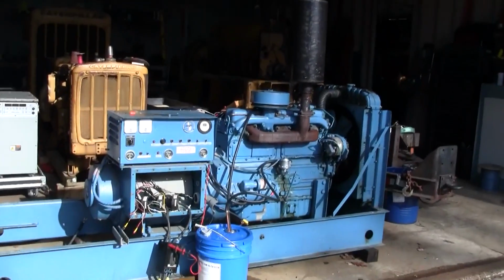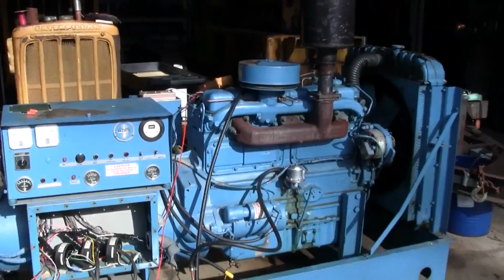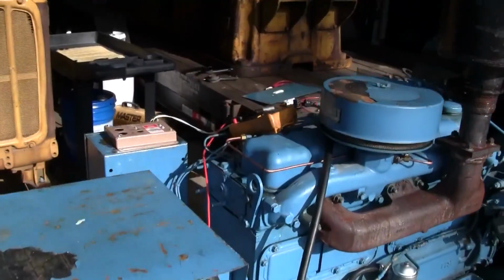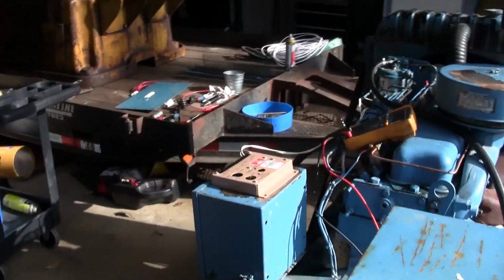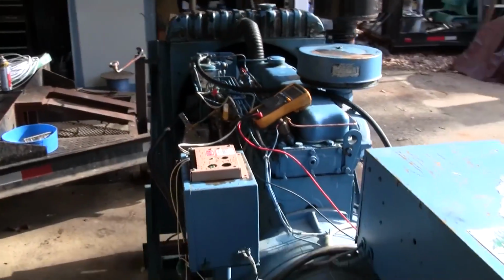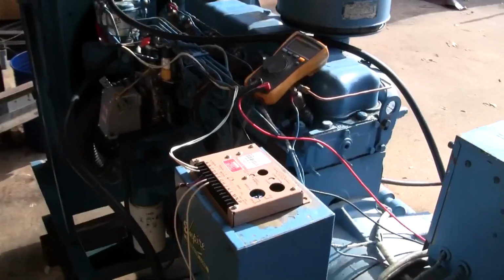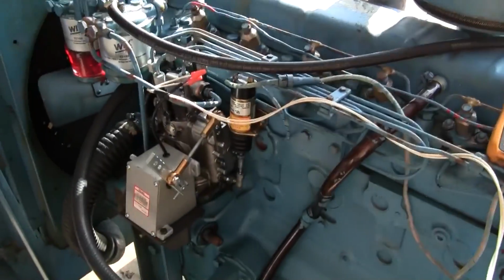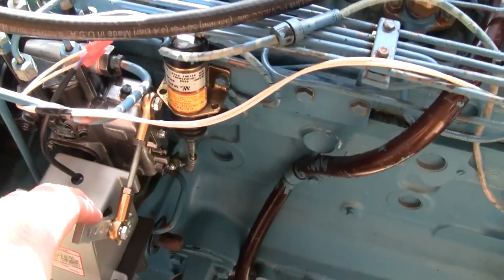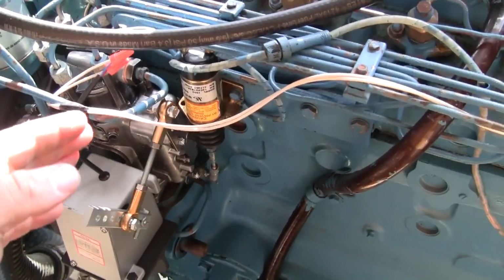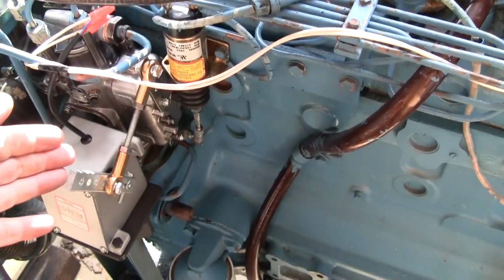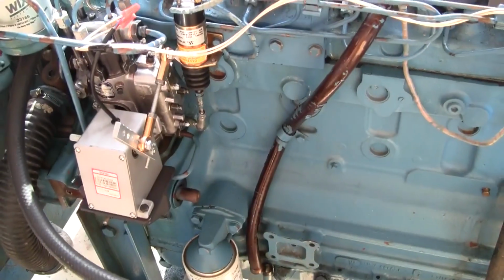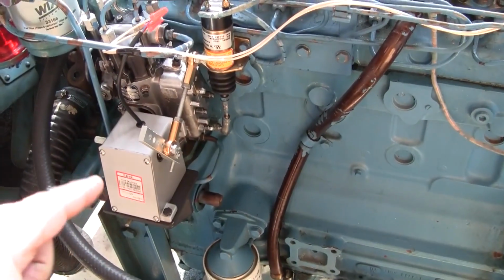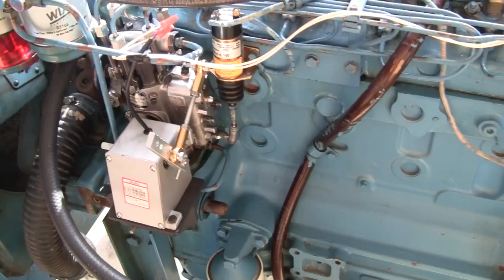Alright, well, I'd consider that successful. I'm quite pleased with the performance of that governor. You know, we were holding 60 to 60.1 hertz between no load and full load. Of course, there's going to be droop. There's going to be a lag. When you dump a heavy load on it, there's going to be half a second or so for the thing to recover and actually get itself back to 60.